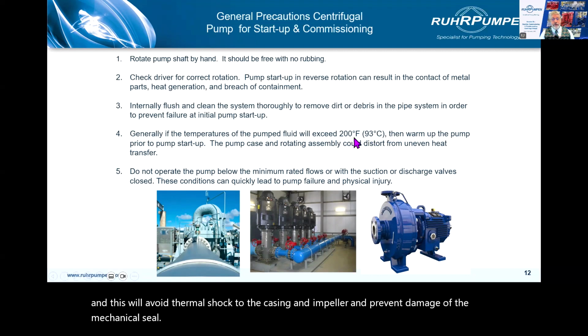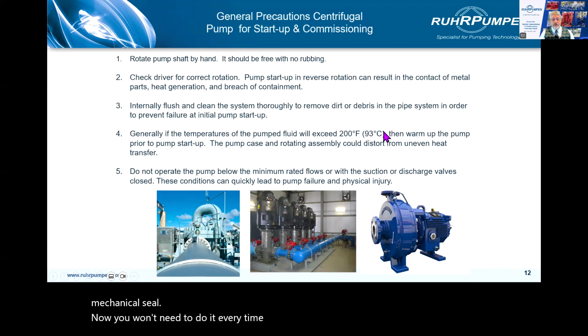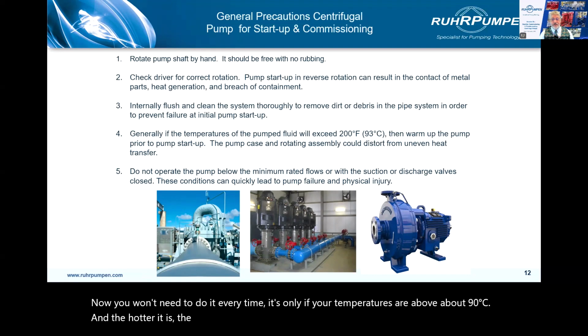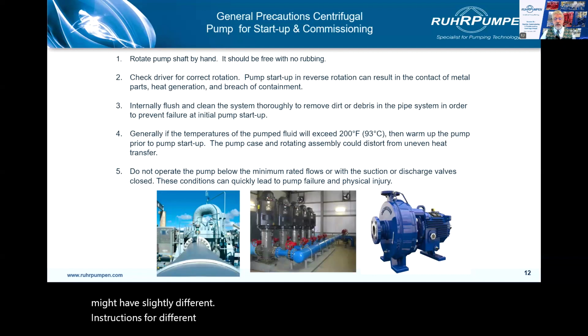Now, you won't need to do it every time. It's only if your temperatures are above about 90 degrees centigrade. And the hotter it is, the more important it is to follow the IOM directions. Each pump vendor might have slightly different instructions for different pumps at different temperatures. The hotter the pump, the more important it is.